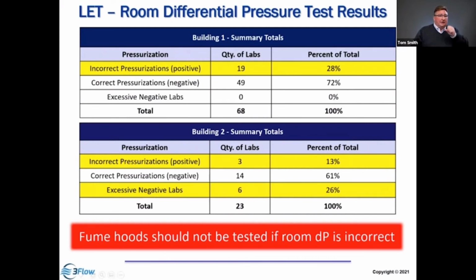And then this space down here wasn't so much a matter of incorrect pressurization, it was excessive pressurization. In that case, you can see the doors are hard to open or close. The airflow coming into the space is very high, causing high cross drafts when we have excessive negative pressurization. It could be a safety issue if the doors are slamming shut. It can also be a safety issue if the cross drafts produced by this pressurization are creating turbulence at the hood.